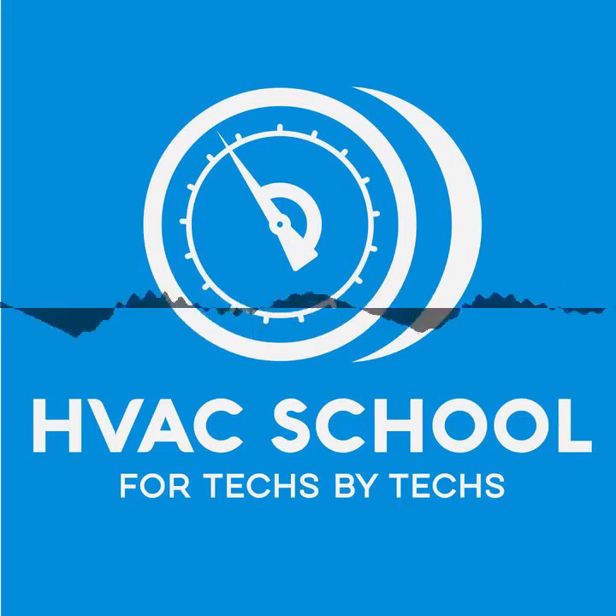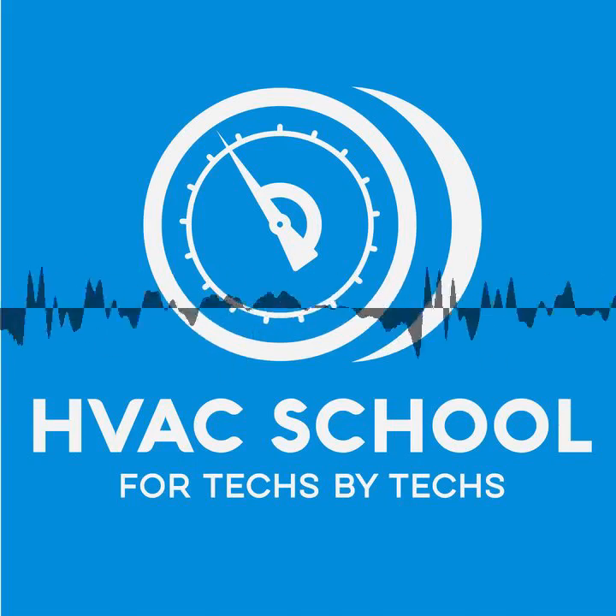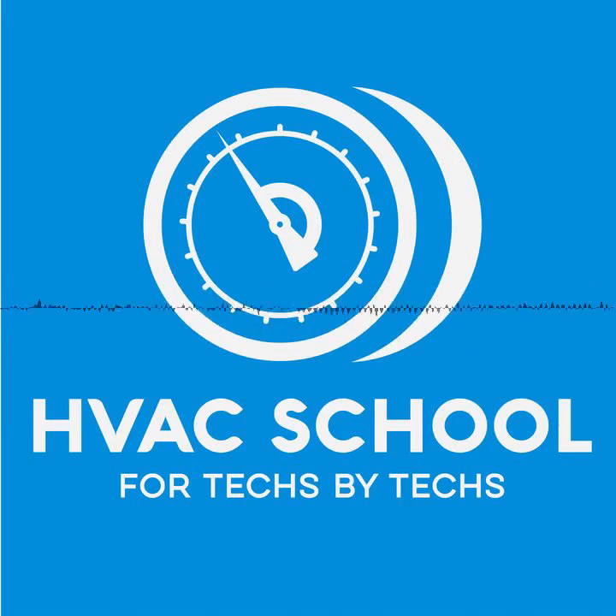So I guess the key thing here is don't discount the value of changing pump oil for the lubrication purposes of it and for it not having those contaminants in it. So it's actually the longevity and the operation of the pump itself, not just the hygroscopic properties of the oil, I guess. Is that a good way of saying that?